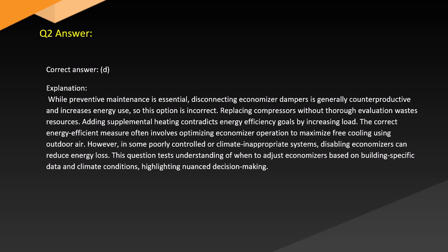Answer. Correct answer, D. Explanation. While preventive maintenance is essential, disconnecting economizer dampers is generally counterproductive and increases energy use, so this option is incorrect. Replacing compressors without thorough evaluation wastes resources. Adding supplemental heating contradicts energy efficiency goals by increasing load. The correct energy-efficient measure often involves optimizing economizer operation to maximize free cooling using outdoor air. However, in some poorly controlled or climate-inappropriate systems, disabling economizers can reduce energy loss. This question tests understanding of when to adjust economizers based on building-specific data and climate conditions. highlighting nuanced decision-making.